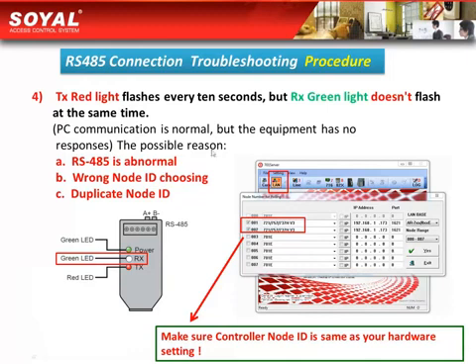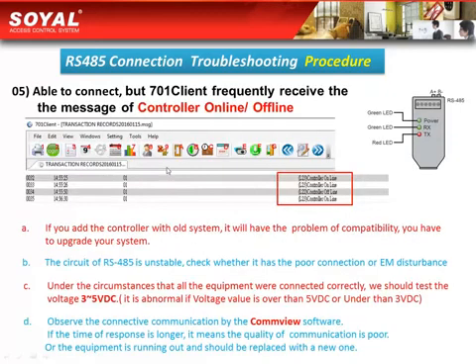When you choose the node ID, make sure the node ID set on the software matches the setting of the controller. Fifth, if RS485 is able to connect but the 701 client frequently receives messages of 'controller online' or 'controller offline,' there may be an intermittent connectivity issue.